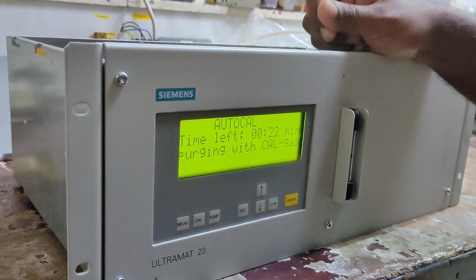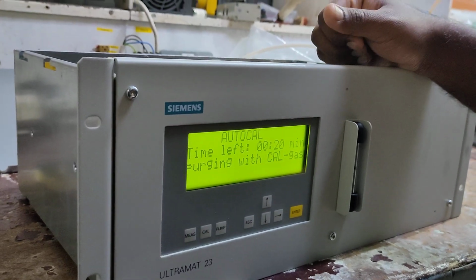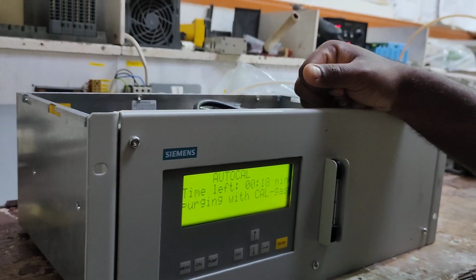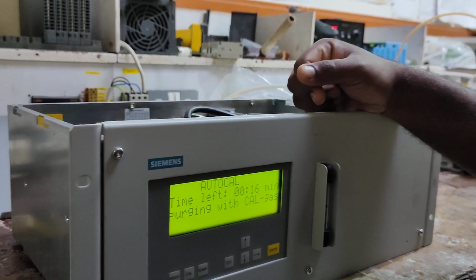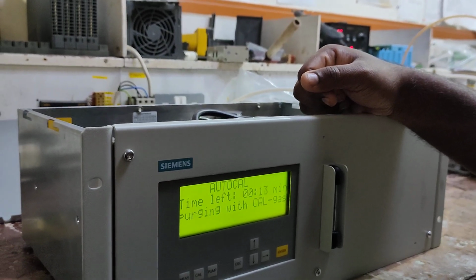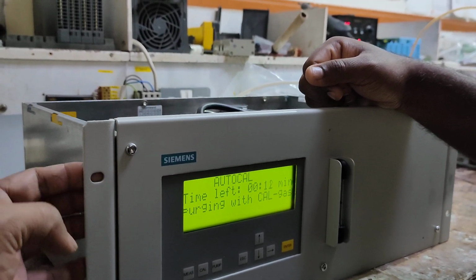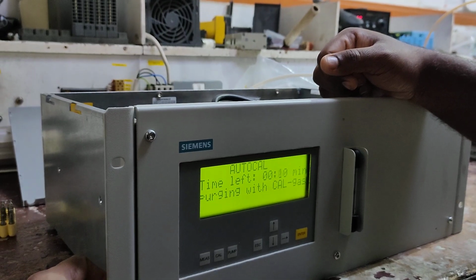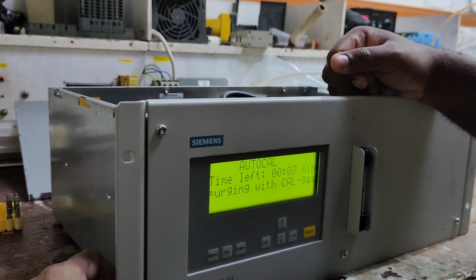Because autocal after warm up is kind of mandatory from the factory. They always say after warm up you should do auto zero. Yes, it is okay, but sometimes just a reset is required. And by mistake, if our people didn't remove the measuring, then it will be wrong in autocal.